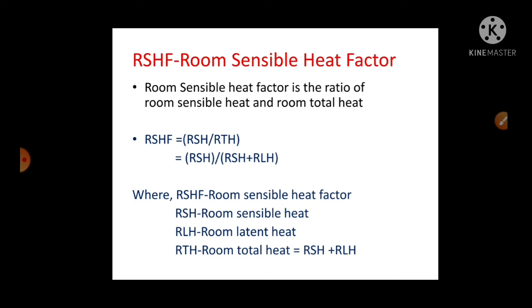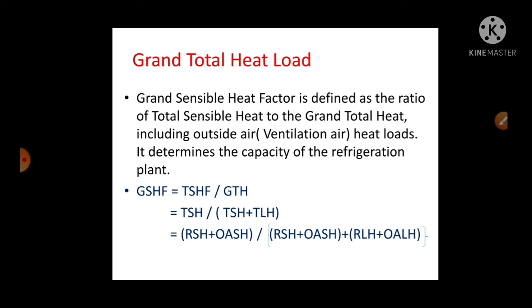So it is a ratio of the... are you getting? So grand total heat. So when we consider the outside air heat, sensible and latent, then the ratio of sensible heat load divided by grand sensible heat load divided by grand total heat load. Grand total heat is what? Total sensible heat plus total latent heat. What is total sensible heat? Is RSH plus OASH, outside air sensible heat, and total latent heat is what? Room latent heat plus outside air latent heat. The ratio of this is nothing but the grand sensible heat factor.